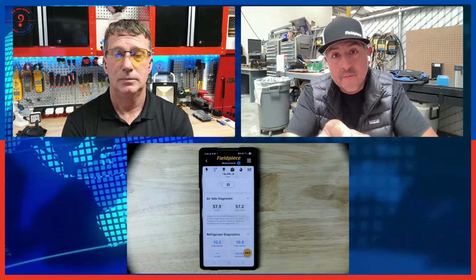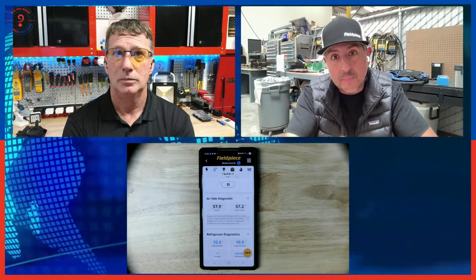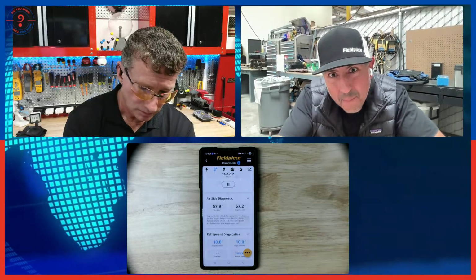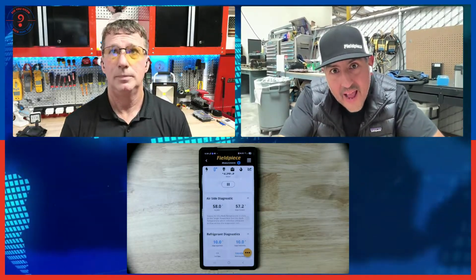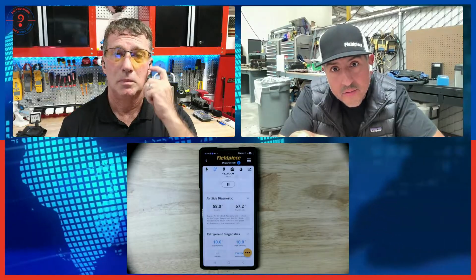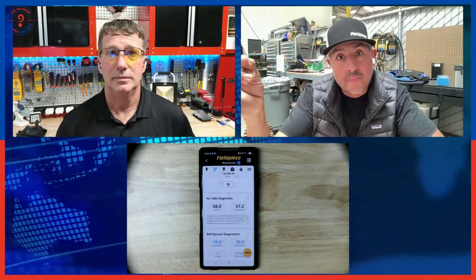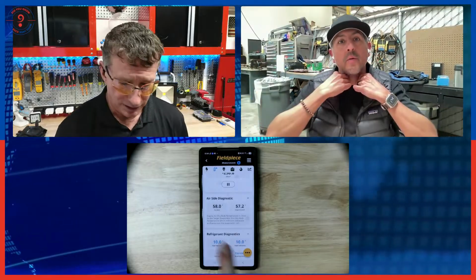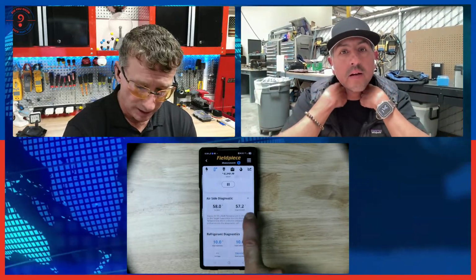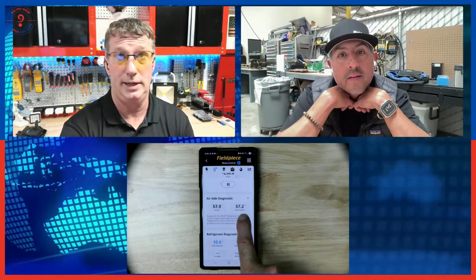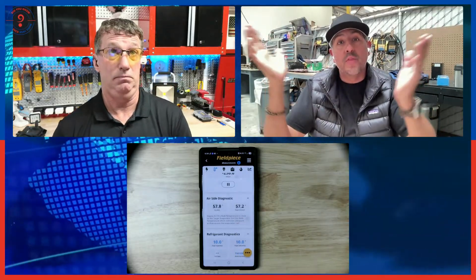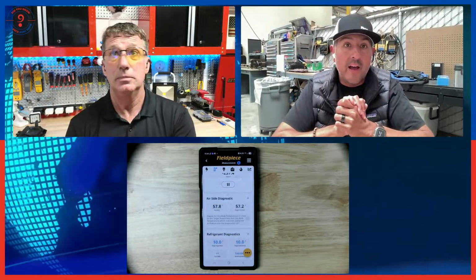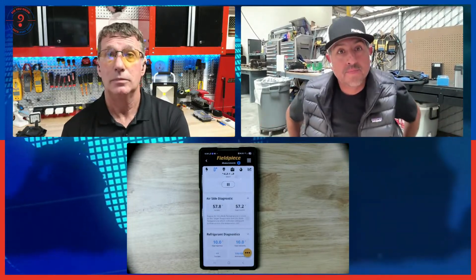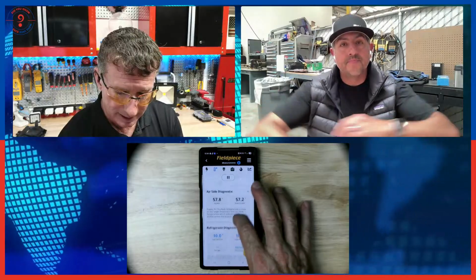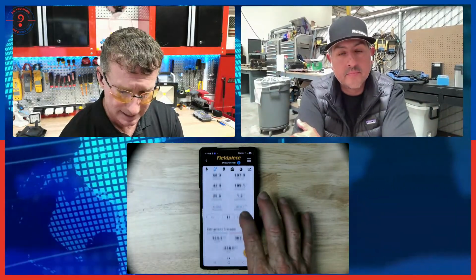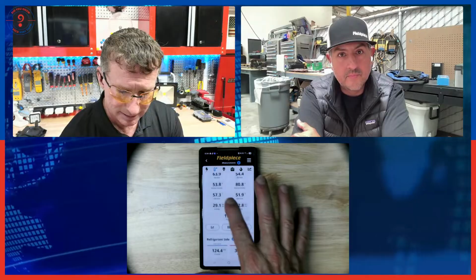In this case, you see the calculated target of your supply air is 57 point something. 57.2. And your actual is 58 dry bulb with a 57.2 target dry bulb. So less than a degree. You're within plus or minus 1, which means you have pretty good heat transfer at that coil right now. Absolutely. I really like the amount of diagnostics that you're starting to add into this.